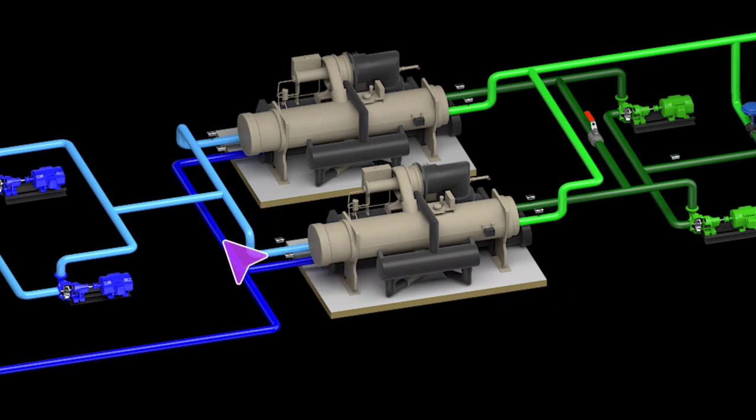You really have to look at the bigger picture of the system. That cooling tower's job is to serve that chiller. Whenever you start running higher temperatures, you're increasing the load on that chiller, increasing the lift and decreasing its ability to cool that system properly. At the same time, when people try to run extremely cold chill water temps excessively, you also get the same effect.